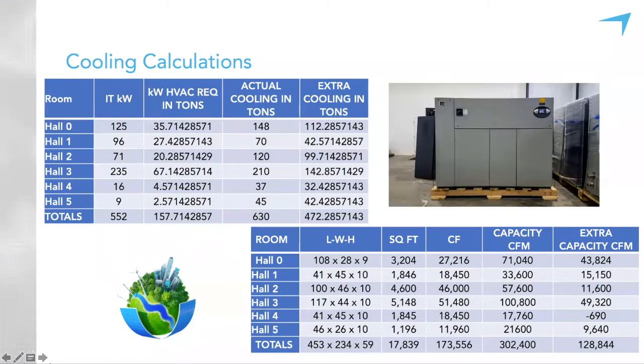Here's an example of 6 data halls that I love to run down. There are 125 kilowatts of IT load in hall 0. If I divide that by 3.5, because 1 ton of cooling will mitigate 3.5 kilowatts of heat, I see their requirement in tons is around 36. I saw that the actual cooling in that room was 148 tons, which came to an extra 112 tons of cooling. Now, this becomes an important point.